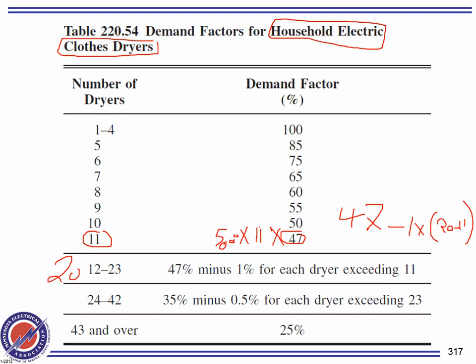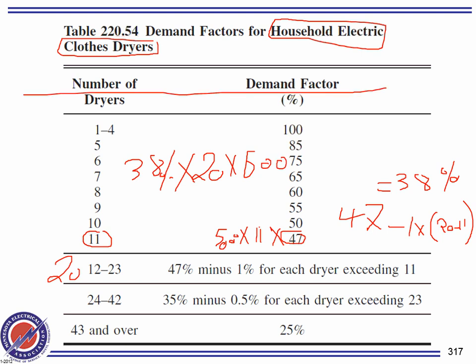So if we have, 38, is it? 38%. Okay, now once I get the 38%, then multiply this by the 20 units that you have. Suppose they were nameplate 6,000. Then you multiply everything by 6,000 and you're done. And that would be the size of the feeder that feeds all these dryers. Obviously, it's not going to feed the dryers by themselves. It's going to feed the whole unit.